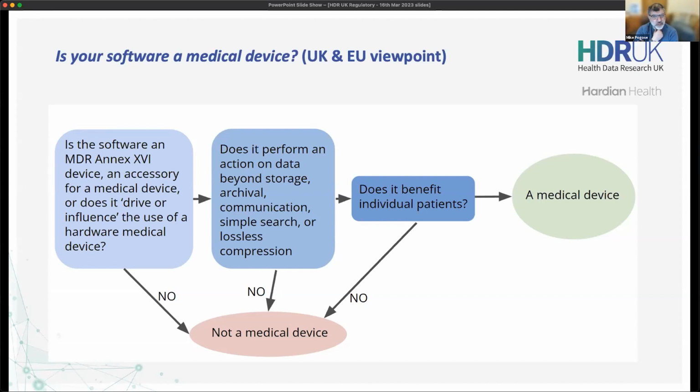And let me give you an anecdote now. Karandeep and I worked a year or two ago on a device which is for cryolipolysis. It's for breaking up fat, reducing fat by cooling skin tissue and heating, but cooling skin tissue primarily. That's an Annex 16 thing. Why is that? It is not a medical device per se, because that sort of thing is more like a cosmetic treatment. It's not really having a medical purpose, but it is listed specifically because of the risk of using that device.